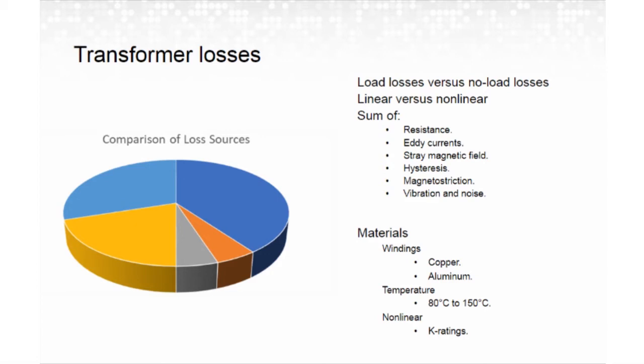In addition, when we consider that our flux leakage can induce eddy currents in adjacent materials, those eddy currents can cause the casing to slightly vibrate and slightly move. So when we're talking about how we reduce that, it would be looking at what we consider the core losses of the transformer, the no load losses. That's why even if you don't put a load on a transformer, it'll still vibrate, it'll still buzz and hum.